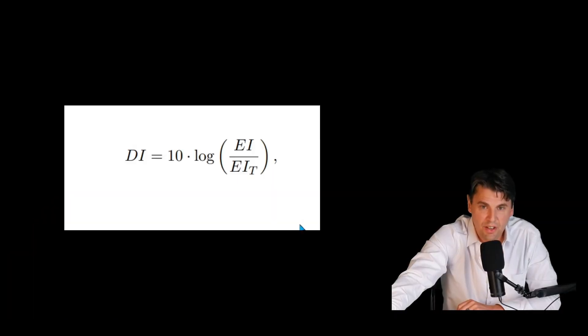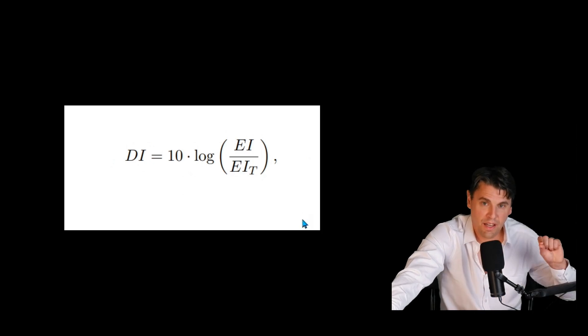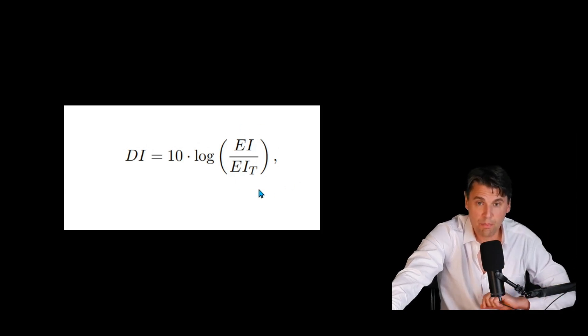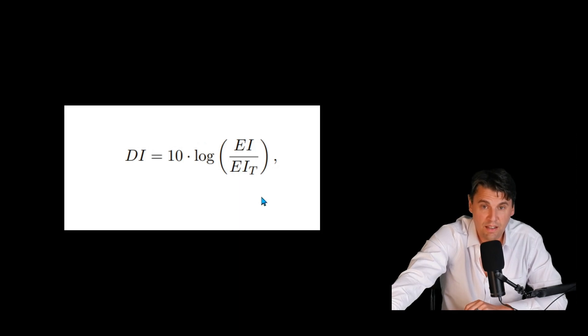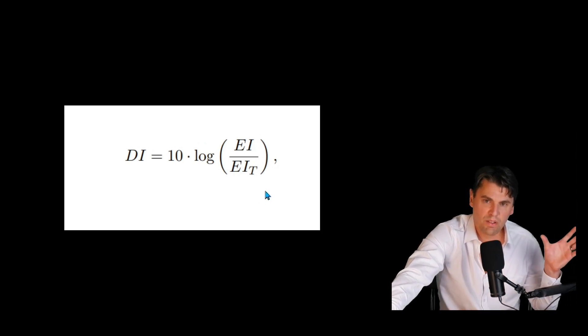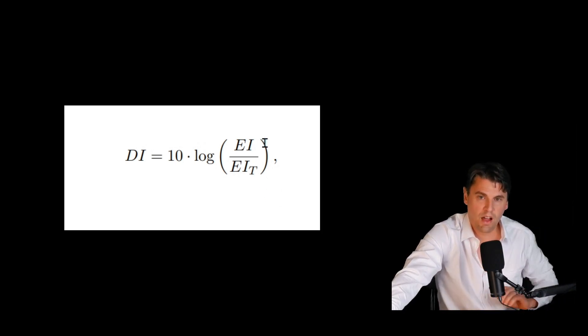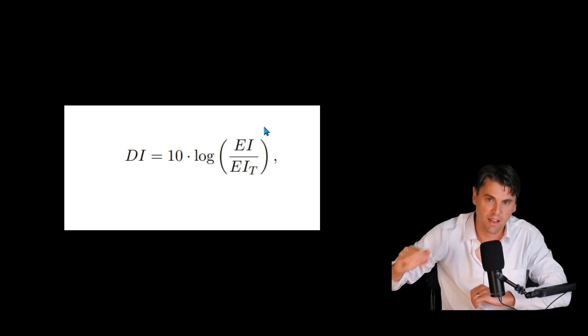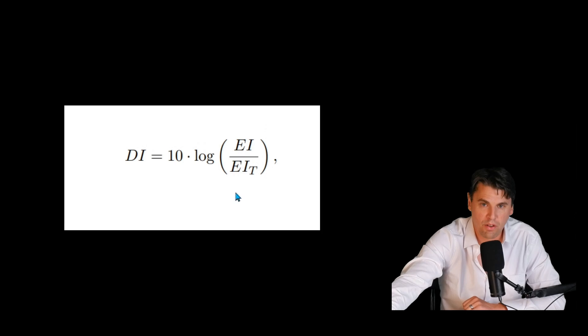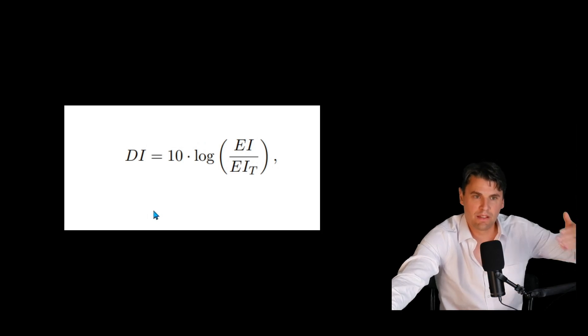Then the definition of our deviation index: if you take your exposure index and you divide by your exposure index that you were targeting, that's kind of the input to the deviation index. And then we also take the logarithm, just so that this won't vary too quickly. The logarithm will kind of compress it and make it vary a little bit more slowly, will give us what we call the deviation index that we can track and see how we're doing as a function of time.